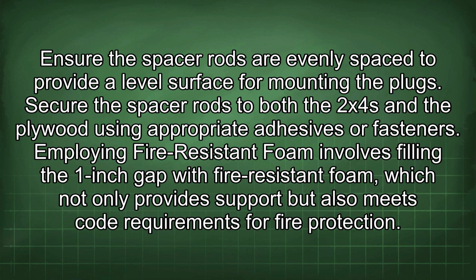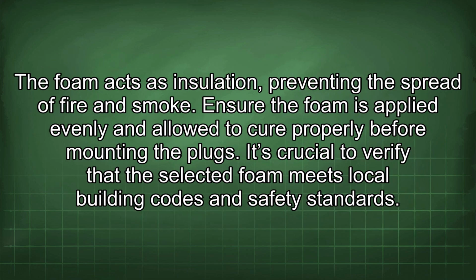Employing fire-resistant foam involves filling the 1-inch gap with fire-resistant foam, which not only provides support but also meets code requirements for fire protection. The foam acts as insulation, preventing the spread of fire and smoke. Ensure the foam is applied evenly and allowed to cure properly before mounting the plugs. It's crucial to verify that the selected foam meets local building codes and safety standards.